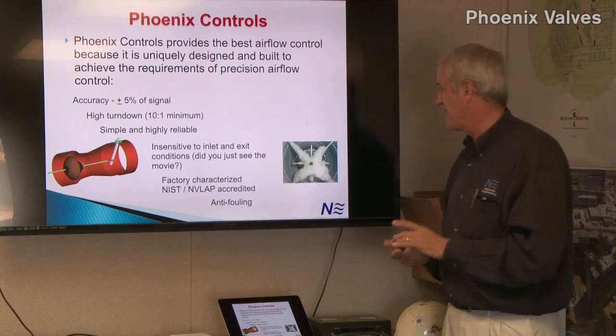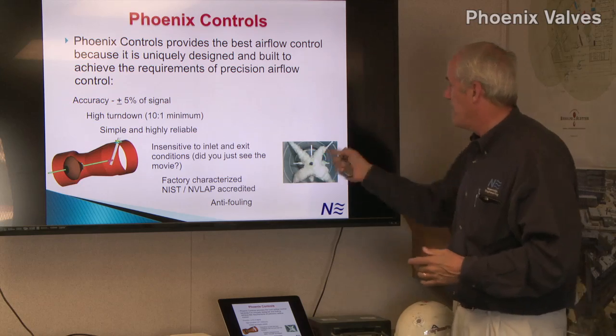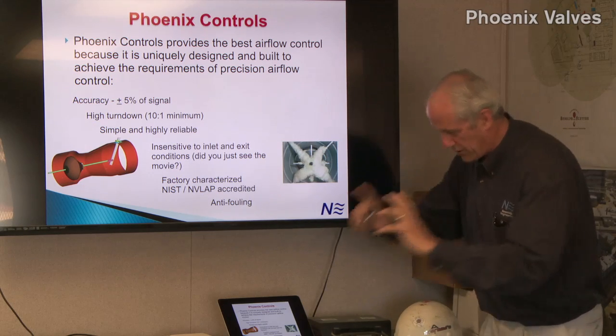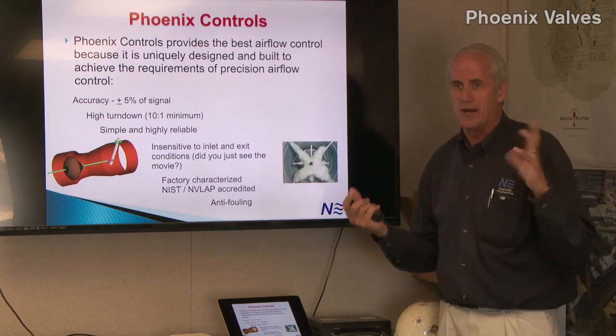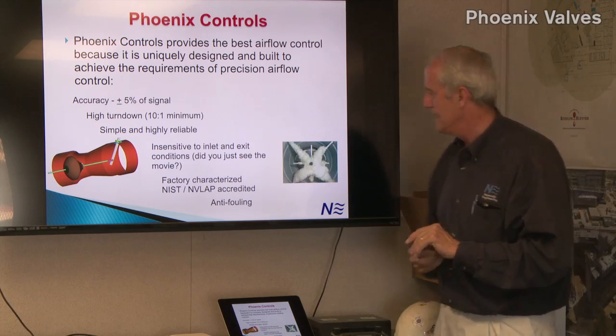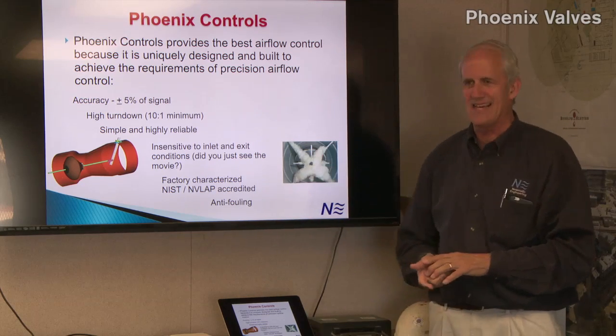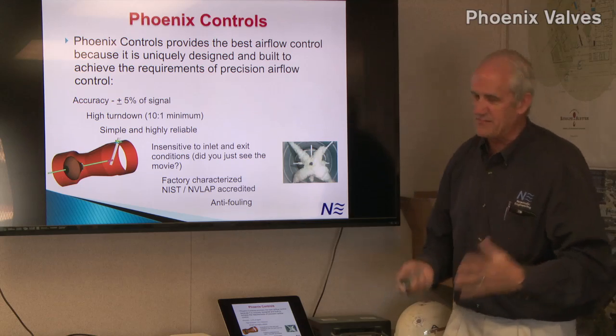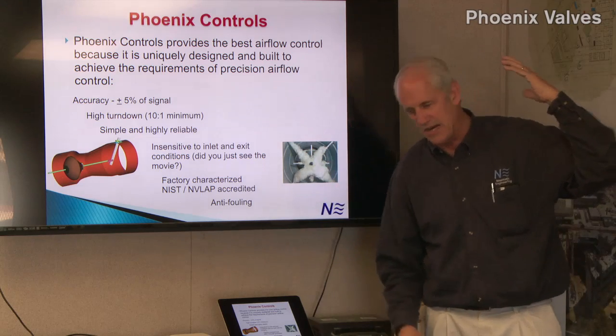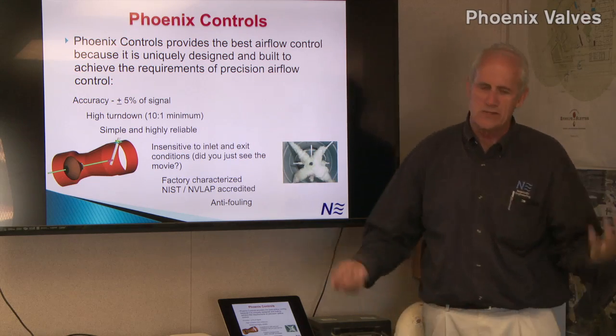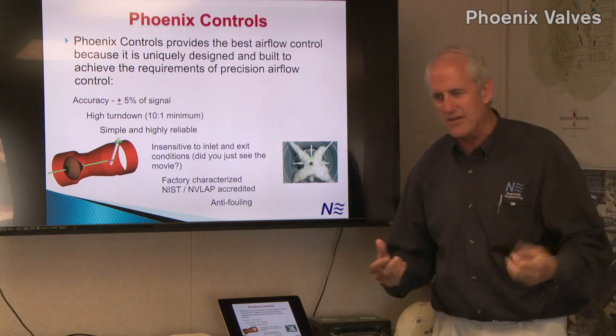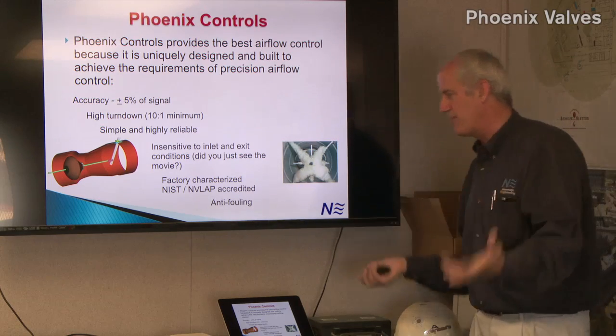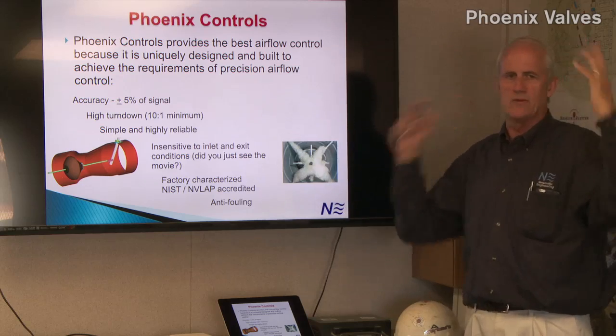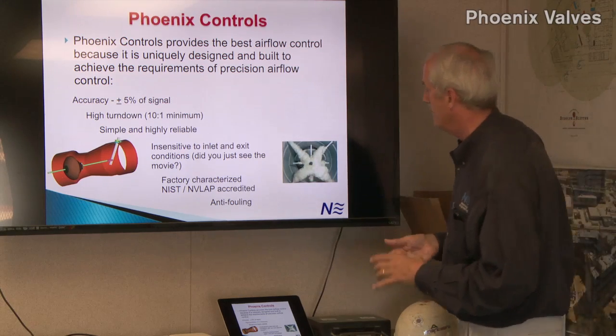We did a job for City of Hope where they were measuring to verify the Phoenix valves. They put in flow measuring stations, real good ones, real high quality air monitoring stations. But on the exhaust side, they got the lint in them. And after 6 months, they called us with a 5-alarm fire. Every one of our rooms, which is supposed to be negative, they're all isolation rooms, they've all gone positive. There was a whole floor of them. I mean, it was a big deal.